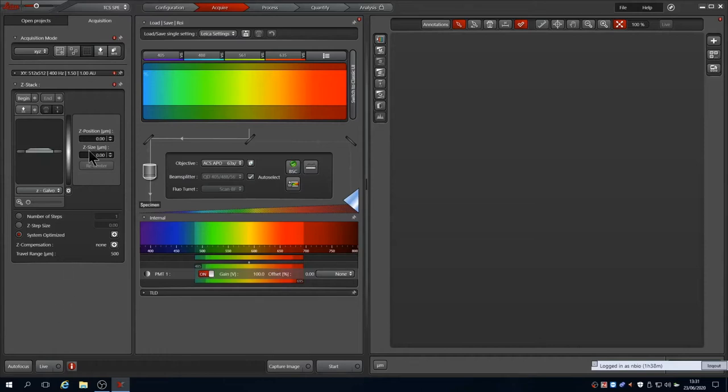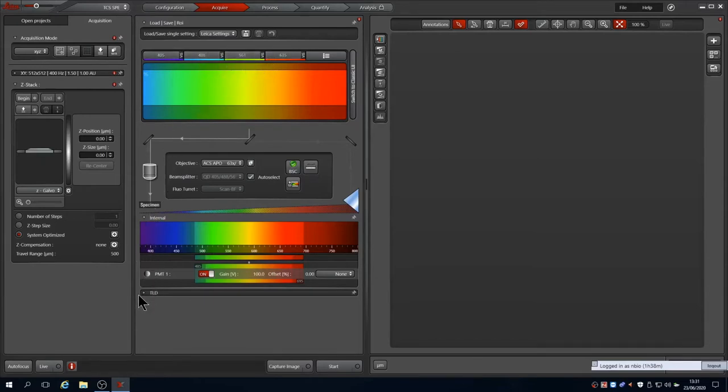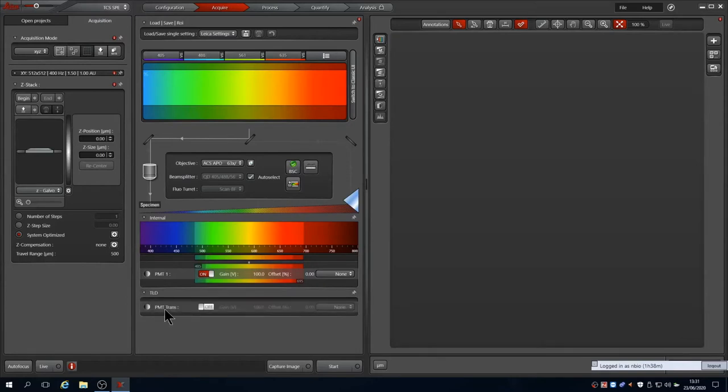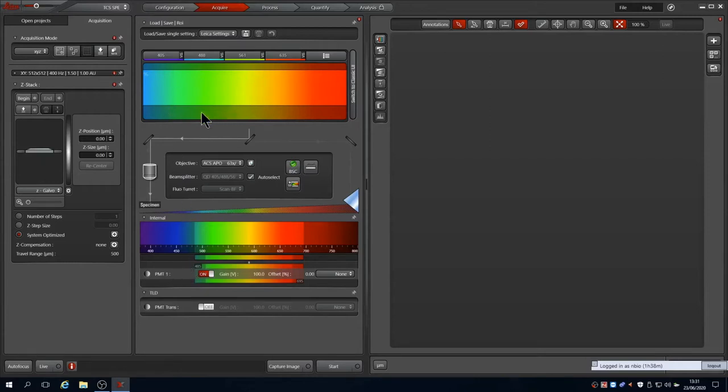In the central pane we can see that there are four laser lines available and one reflected light detector for fluorescence, PMT1, which has a variable band pass filter. There is also another detector for transmission allowing a bright field image to be captured with the laser light passing through the sample. By default PMT1 is active and no laser lines are on.